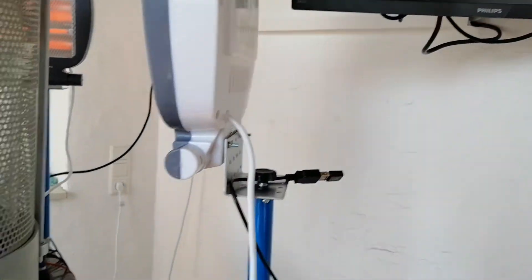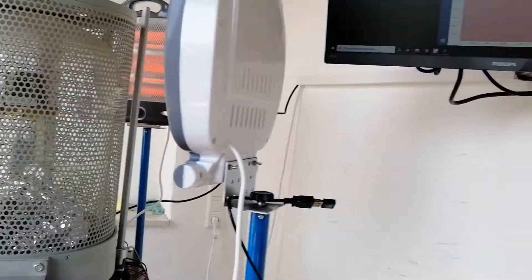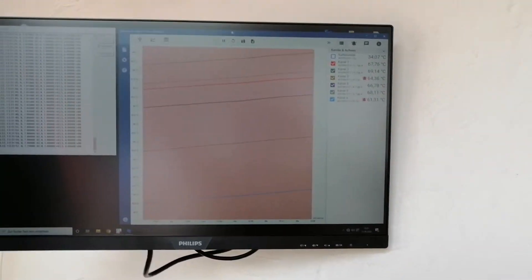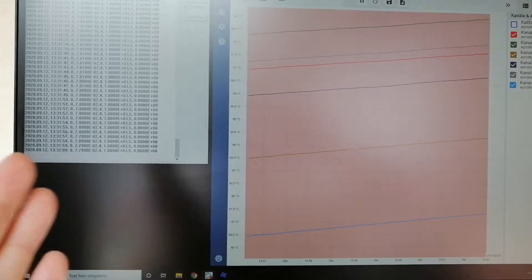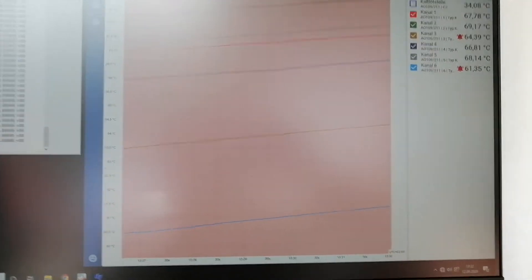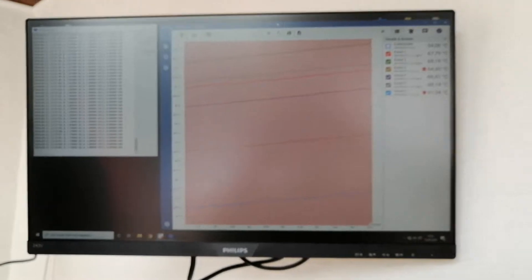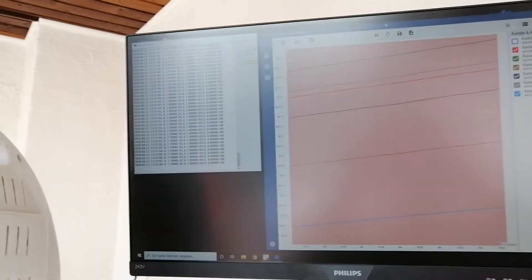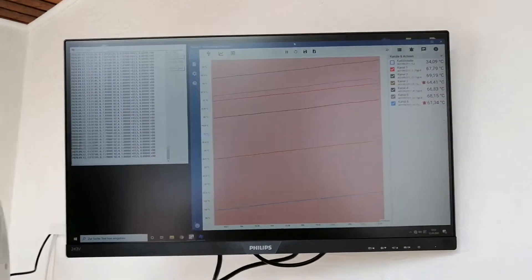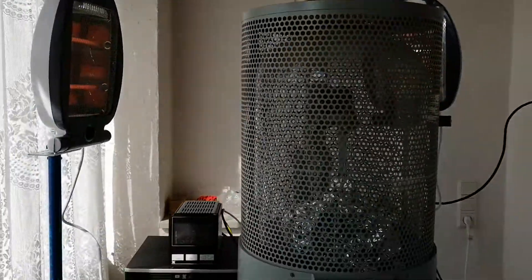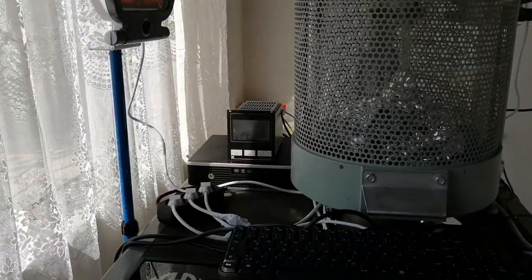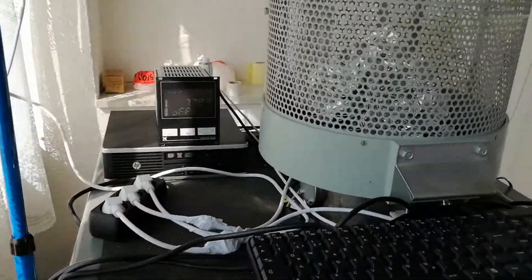We need to provide graphs for pressure and temperatures over six hours. They must meet requirements like in the 10 to the power of minus four millibars. I hope the diffusion pump will get to minus five. It does usually.